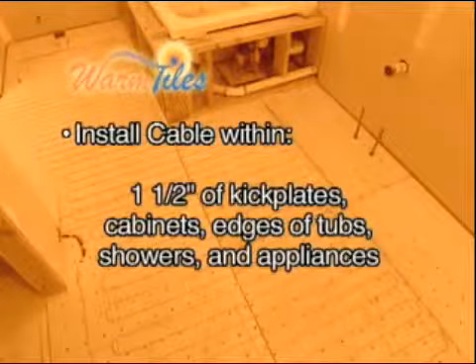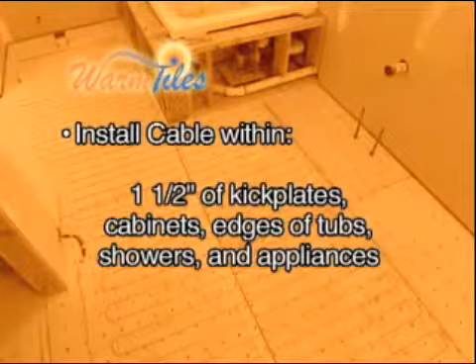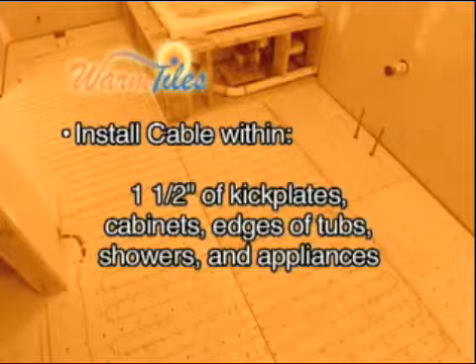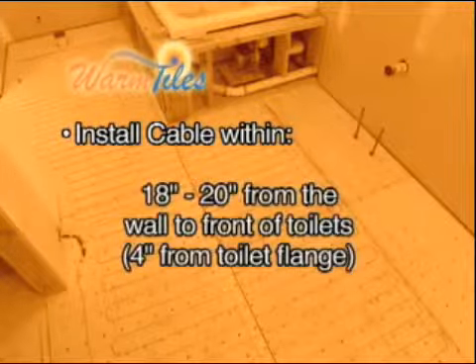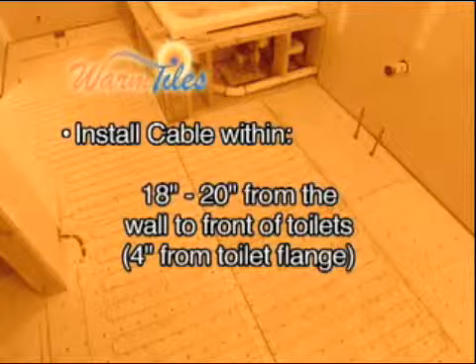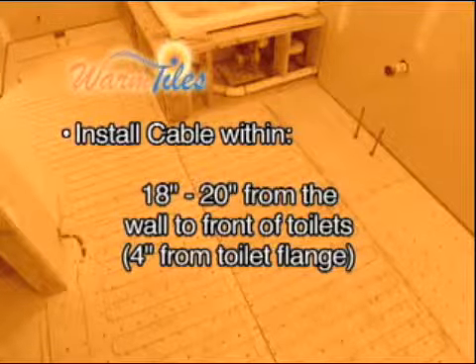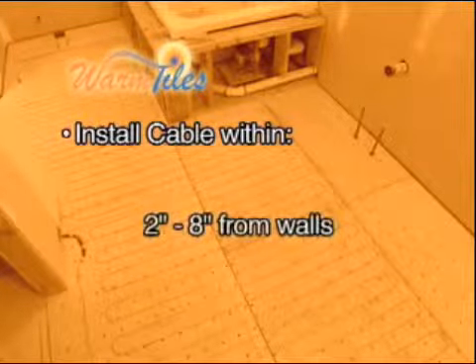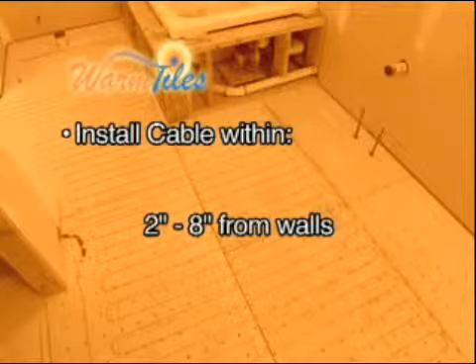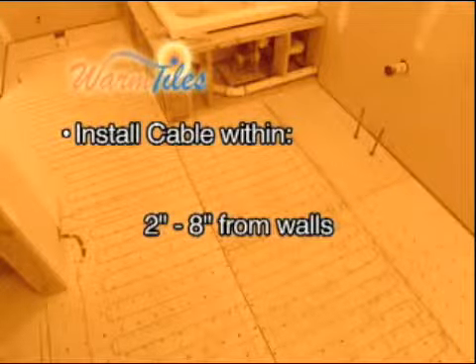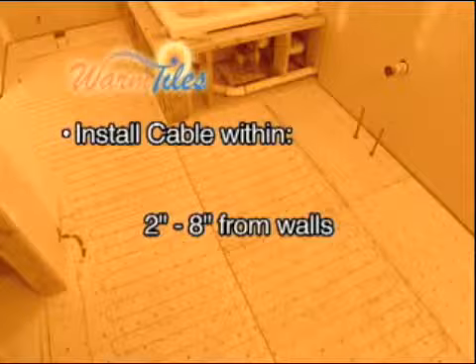The cable should be installed within 1.5 inches of kick plates on cabinets, edges of tubs, showers, and appliances, 18 to 20 inches from the wall to front of toilets, making sure to be 4 inches from toilet flange, and 2 to 8 inches from walls as referenced in the warm tiles installation instructions included in your kit.